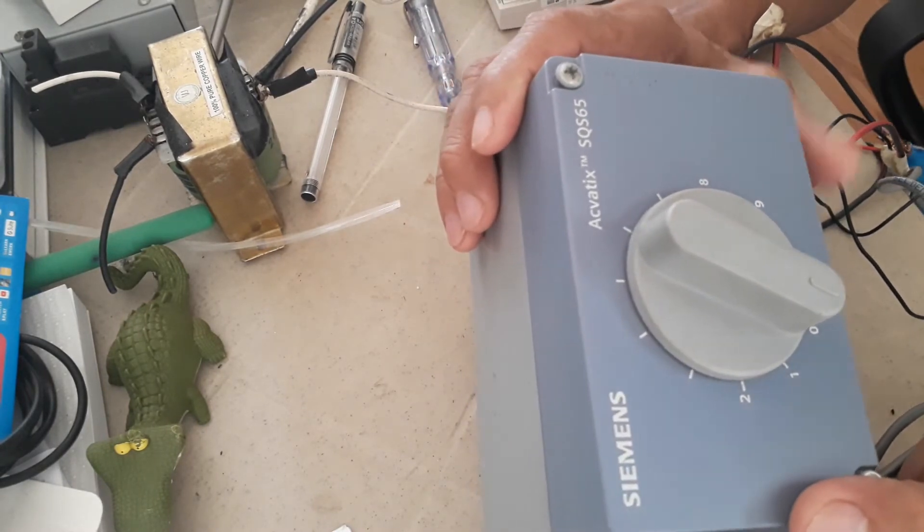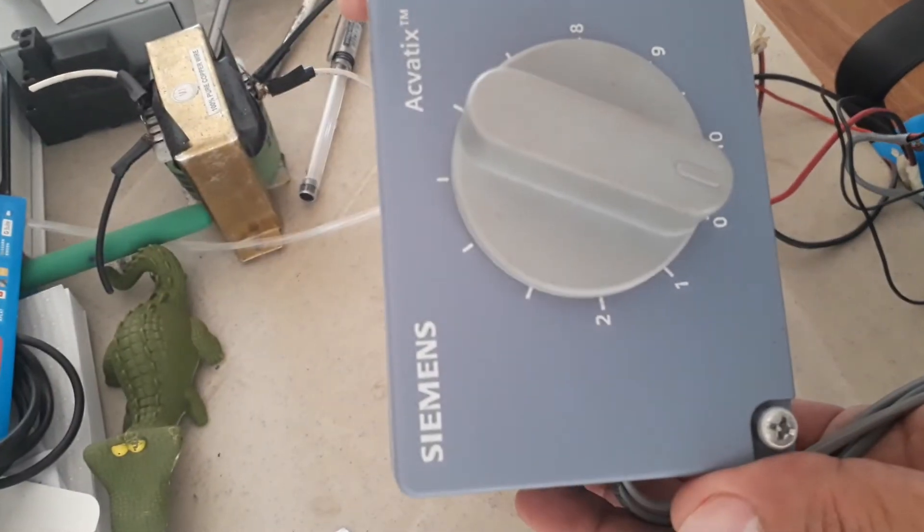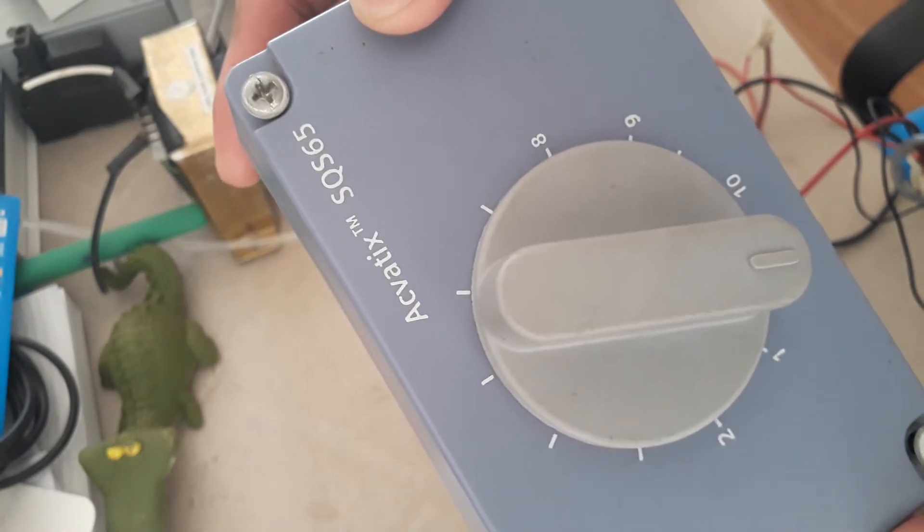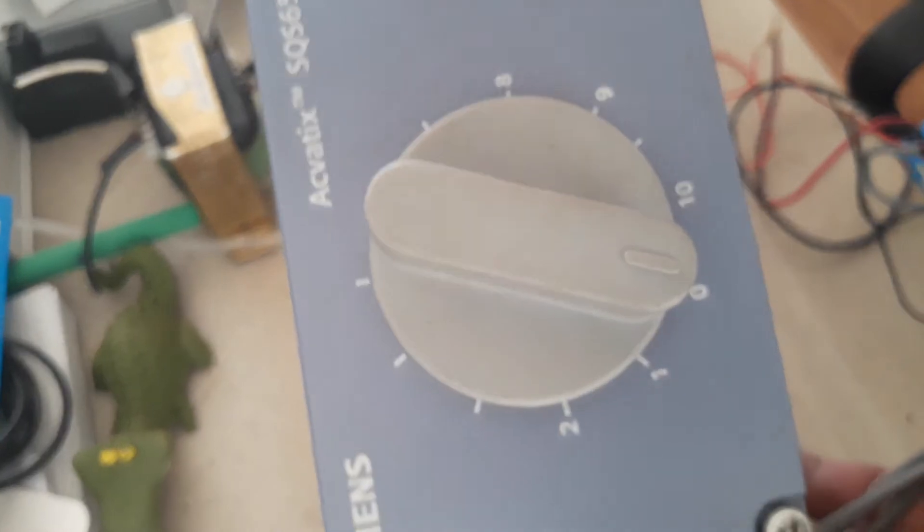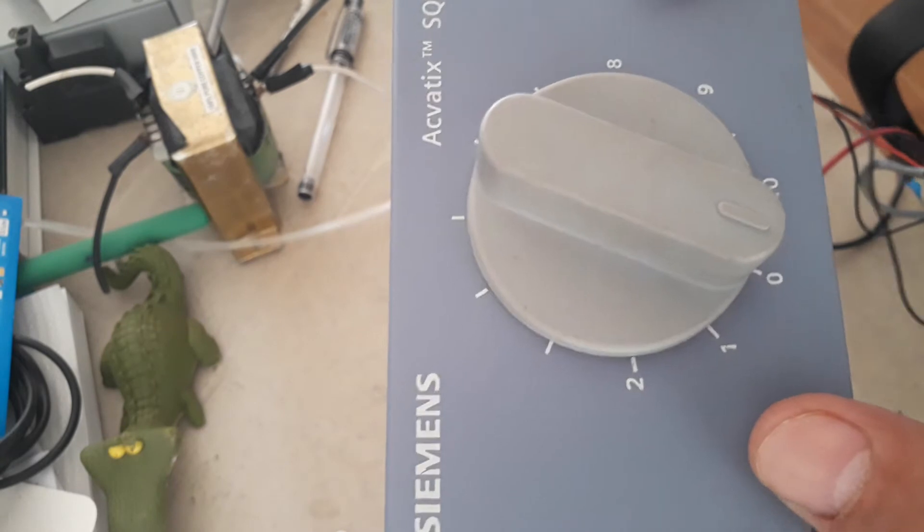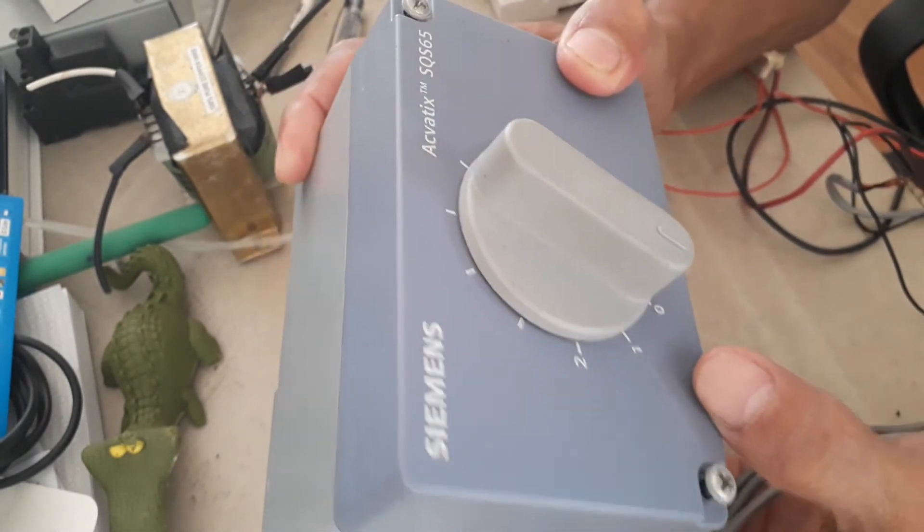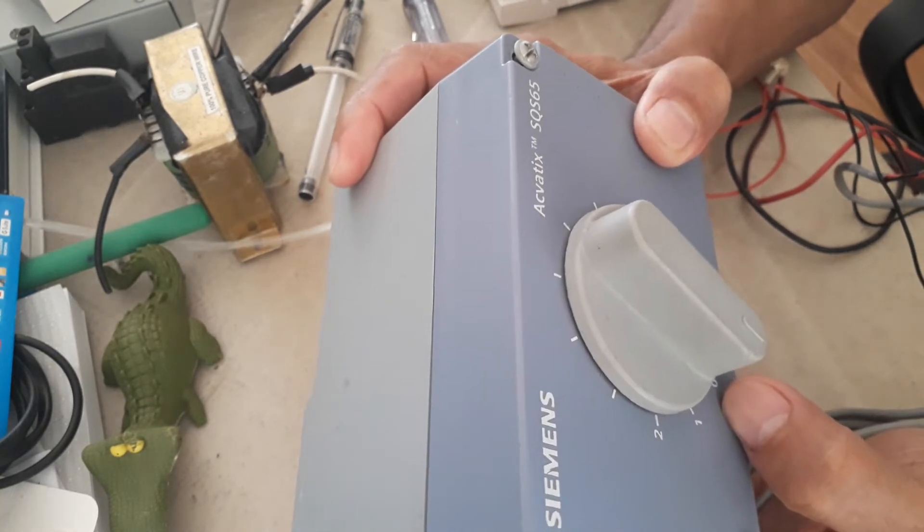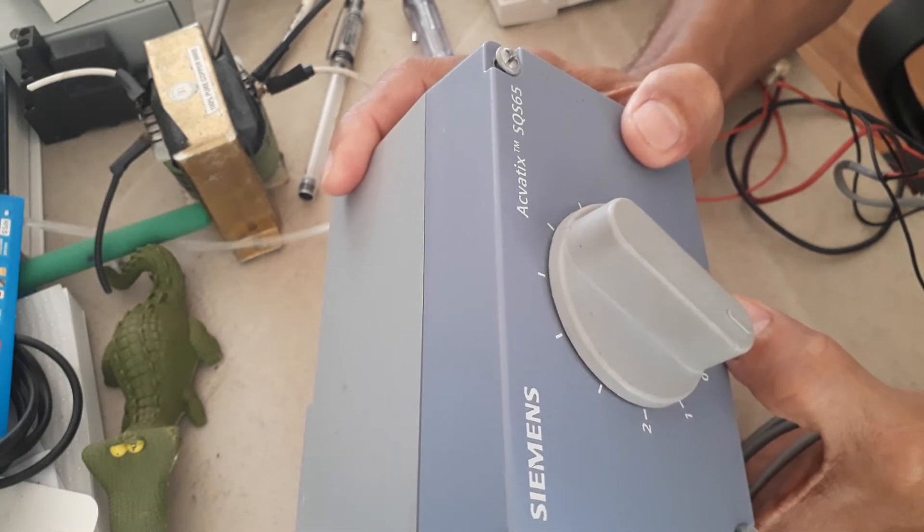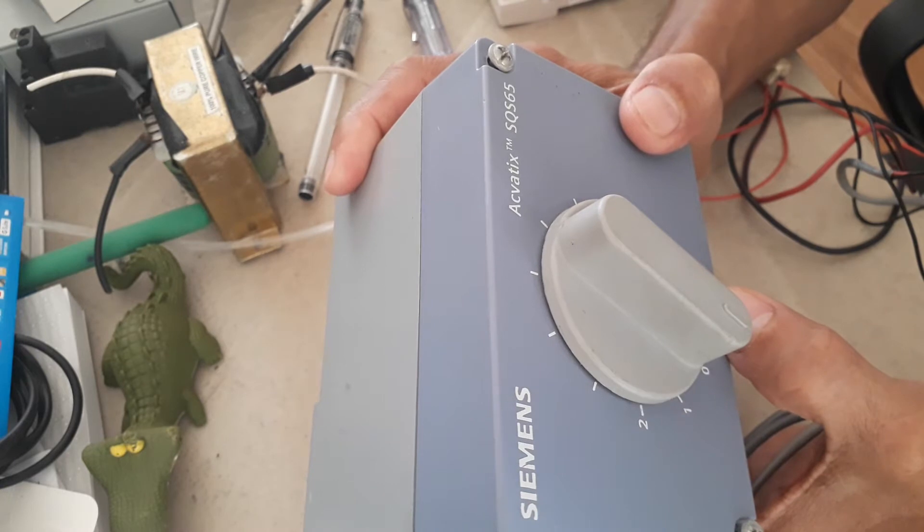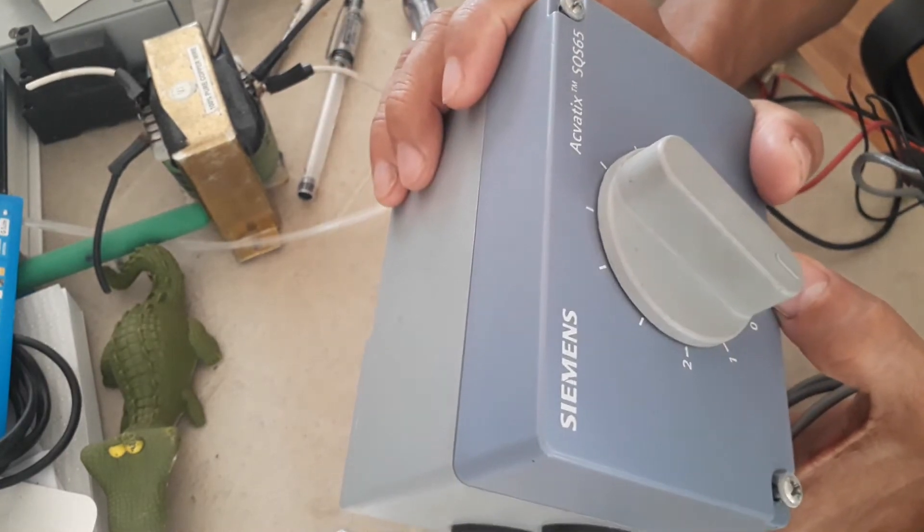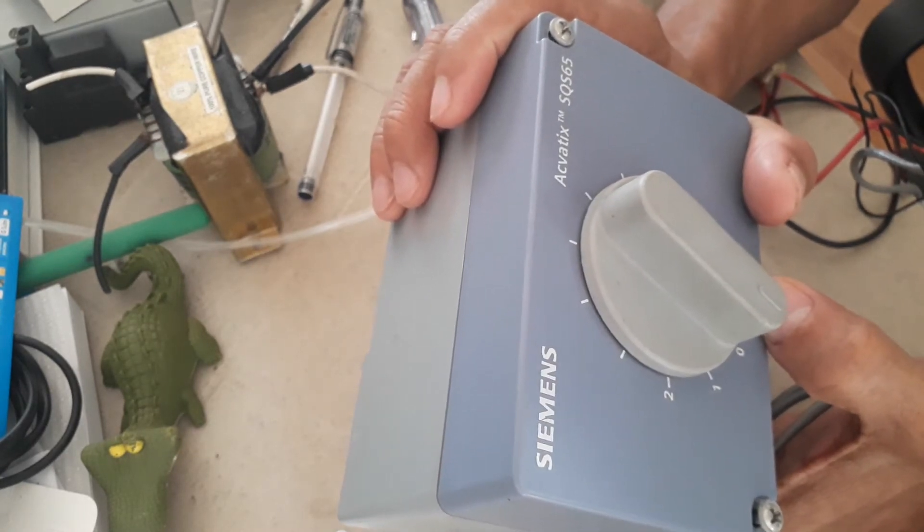Actually, this is a valve actuator by Siemens. This is model Acvatix SQS65. This knob is the one that will show you what is the current opening of the valve actuator. As you can see here, 0 up to 10. So this valve actuator can open the valve 0 to 100% opening. The control for this valve actuator is modulating.